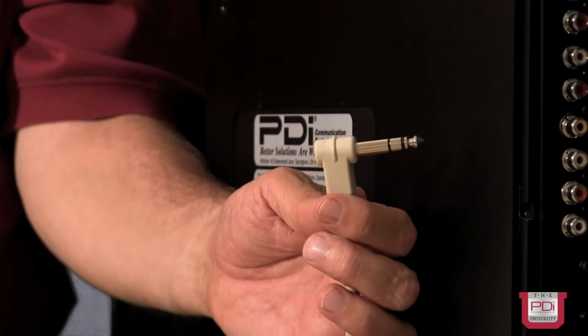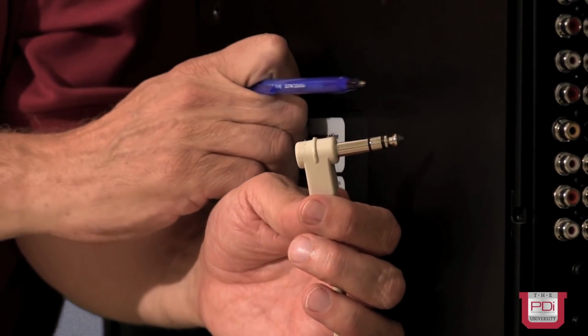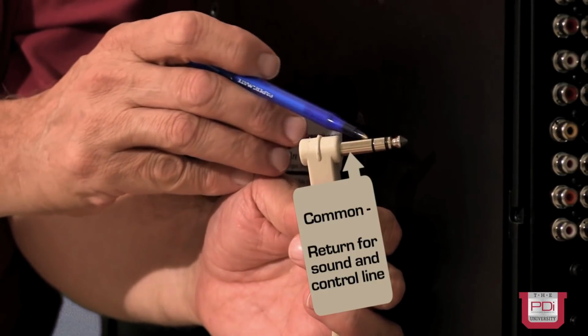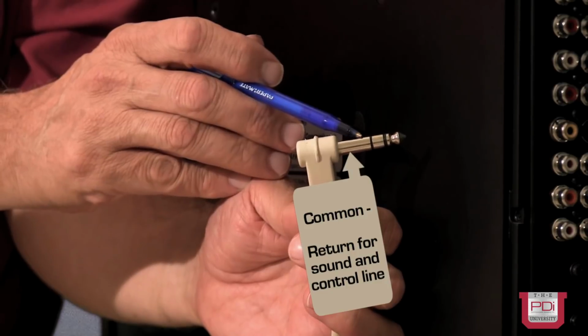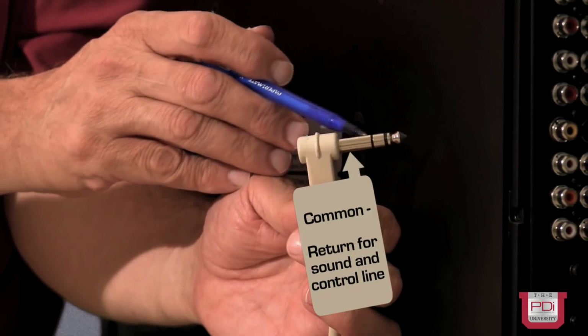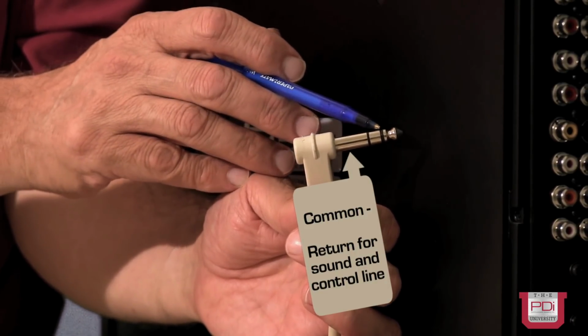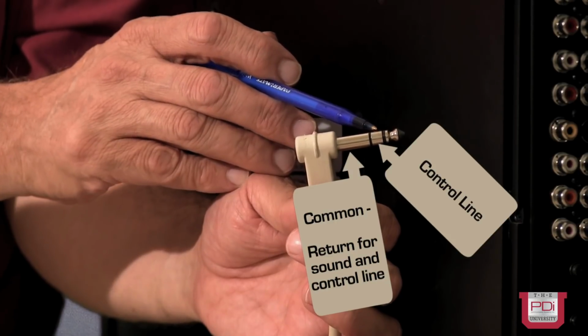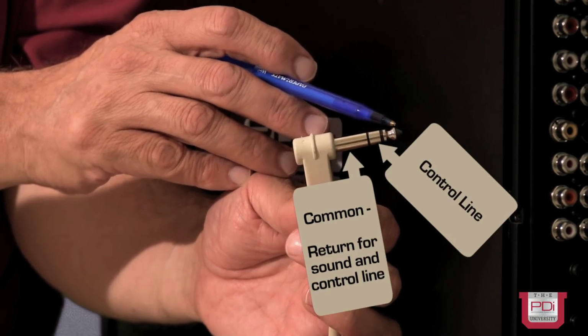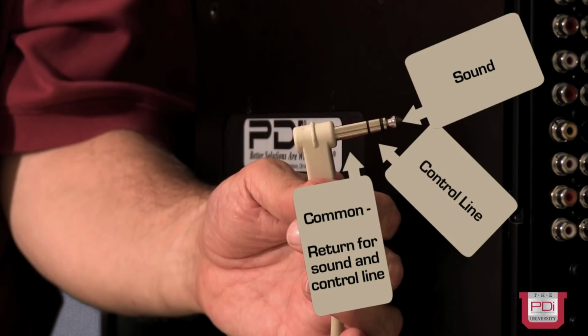Healthcare TVs are in general wired through a 3-wire interface. The common of the signal line connects to the big metal band, which is common. The center metal ring is the control line, and then the very tip carries the TV's sound.